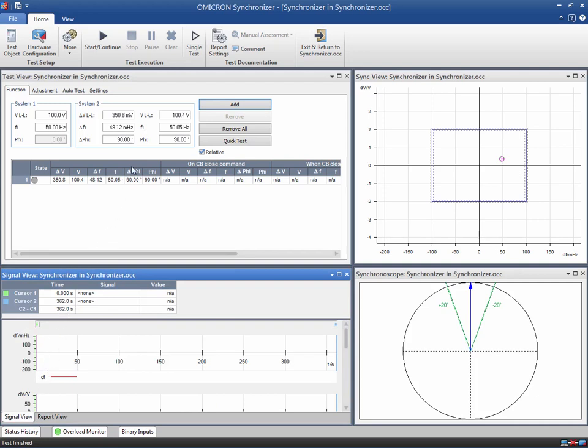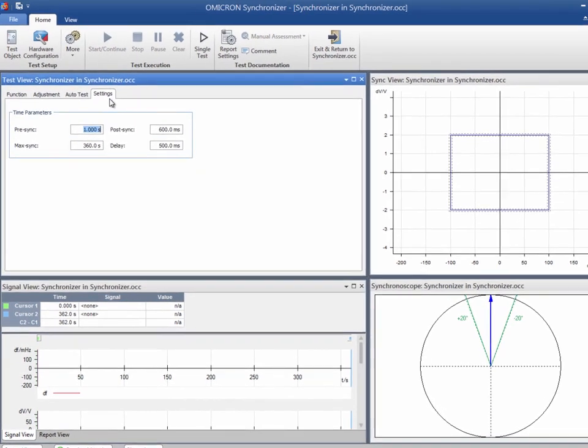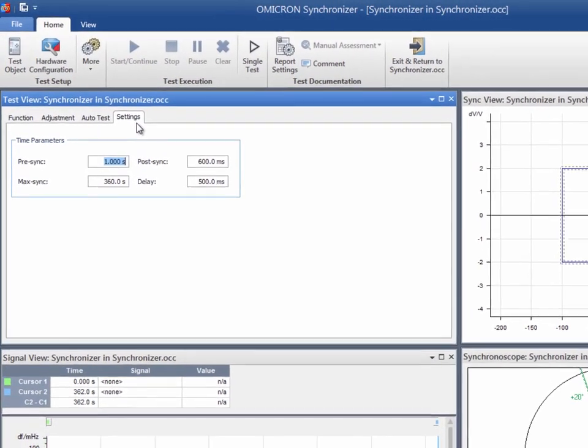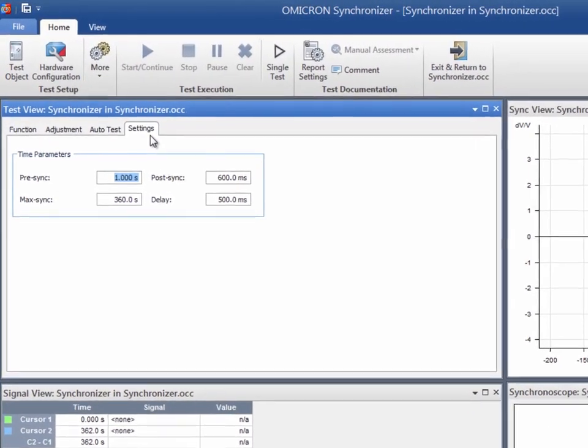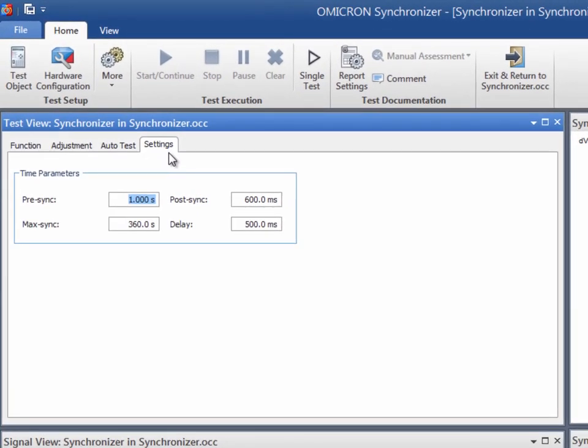Now we will focus on the settings of the test view. The settings tab contains common testing parameters that are used by the different test modes: function, adjustment, and auto test modes. During the pre-synchronization time, the voltages are output by the CMC test set, but no start signal is issued to the synchronizing relay. This allows the voltages to stabilize.